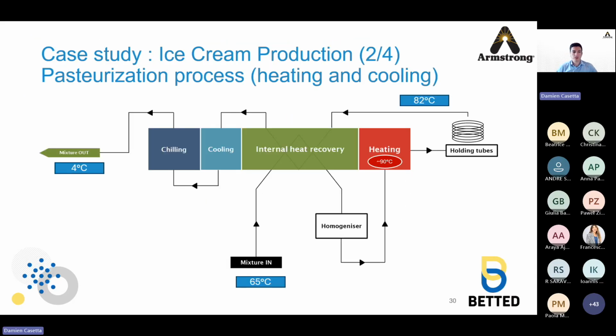Let's take a closer look at the pasteurization process with its own heating and cooling need. So if we follow the mixture entering the pasteurizer, it enters at 65 and then goes into this internal heat recovery to get more heat, homogenizers, and heating at 90 degrees approximately. But after that, it's going at approximately 82 in the heat recovery again to get some cooling and heating, what we've just seen, entering the cooling step to get to a further lower temperature, and chilling to reach an outlet temperature of 4 degrees.